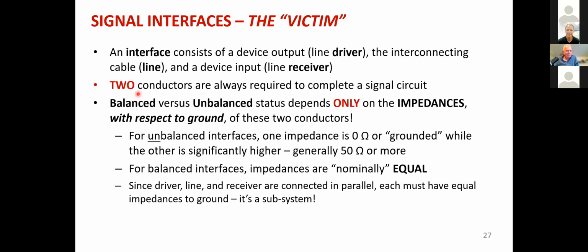So there are 2 kinds of interface for signals. There are balanced ones, which use the same 2 wires that an unbalanced one does, but in an unbalanced interface, we ground one of the conductors. But the important point I want to make here is that the status or definition of an interface depends only on the impedances with respect to ground of those 2 conductors. If we have a 0 ohm impedance on one of them, the grounded one, that automatically makes it unbalanced, because the other line is going to have some higher impedance, the one that has a signal, anywhere from 50 to a few thousand ohms. For a balanced interface, we try our best to make the impedances of those 2 wires with respect to ground equal.